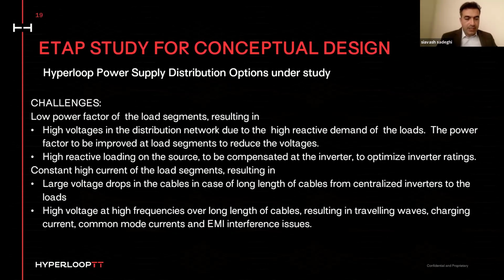2 main challenges that we have for the 5 kilometer concept design is high inductive load. So we are putting together the modules of linear motors, which creates a high inductance load. And since we are at the maximum acceleration and maximum deceleration, because we have a short track and we want to get to the maximum speed and decelerate, we have maximum current most of the time on the motors. So maximum current, high inductance, which bump up the voltage a lot. So we would like to know if we need to put some step down, step up transformers, if we need to put power factor correction at the motor side, at the DC bus side. These are the things and challenges that we are facing right now.